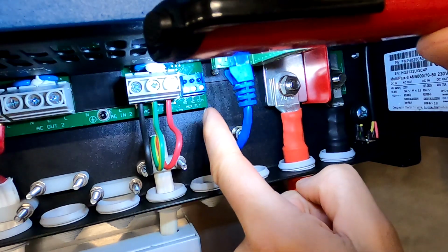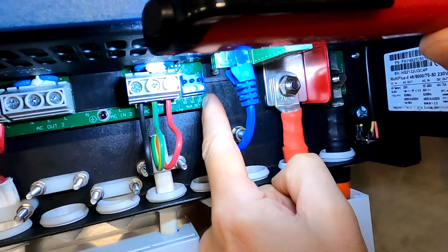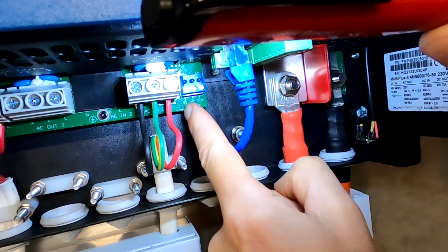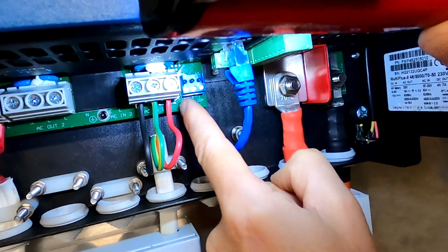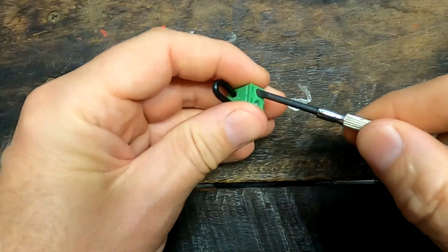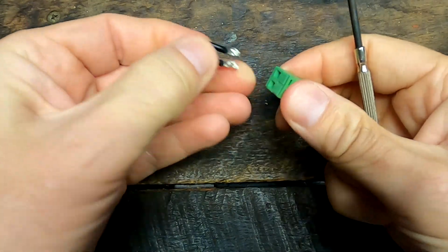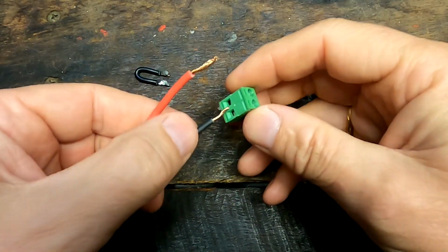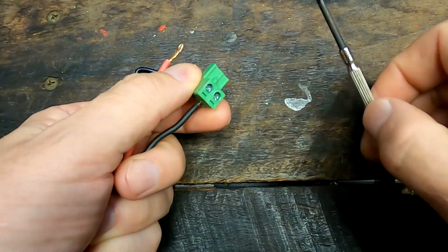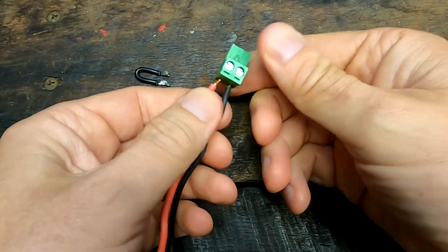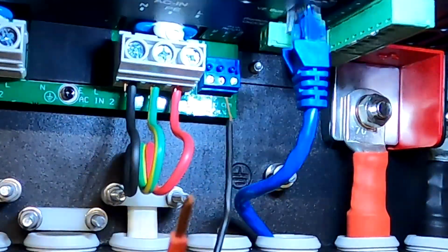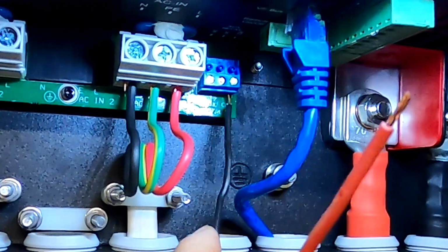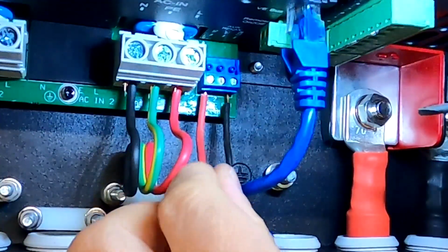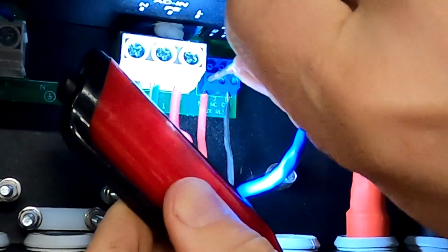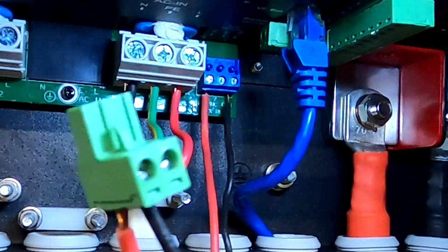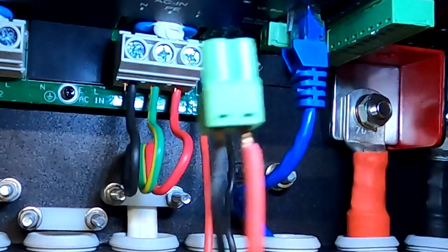So we would need to connect the Phoenix remote on-off switch between COM and NO, normally open. If the relay turns on internally, we have a pass-through between COM and NO. Then we just take these two wires here as our test wires and see if it actually works. So we have one going into the COM port, and the other side here is connected to our plug, which goes into the Phoenix inverter.